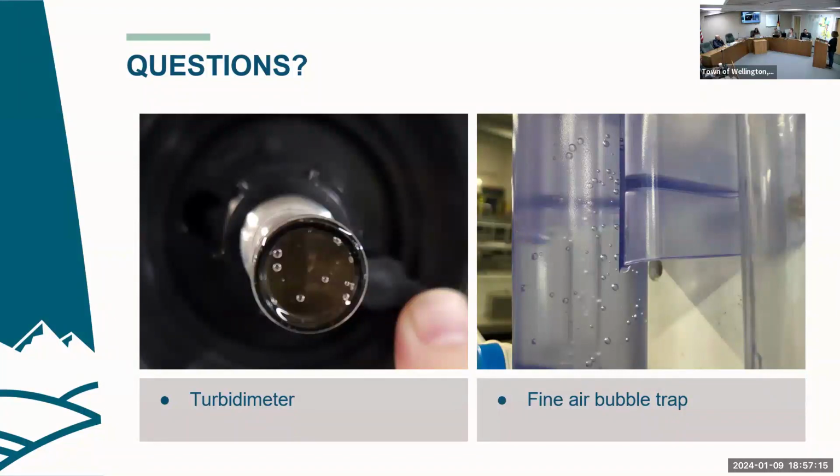If you take your kitchen sink, for example, and the aerator installed on it, and pour yourself a glass of water and measure that with a turbidimeter right out of the tap, you would see very high turbidity, only because there are air bubbles suspended in that water. So there were no quality issues in this case, just air bubbles suspended in the water.